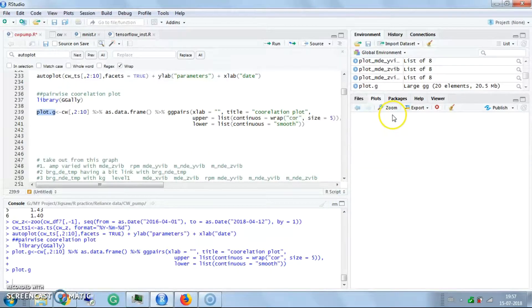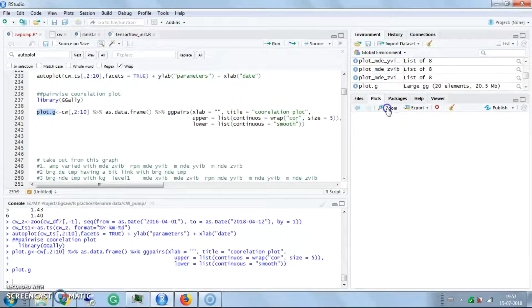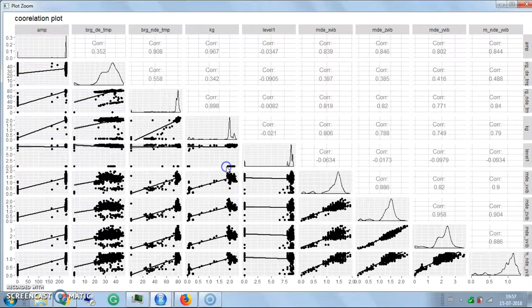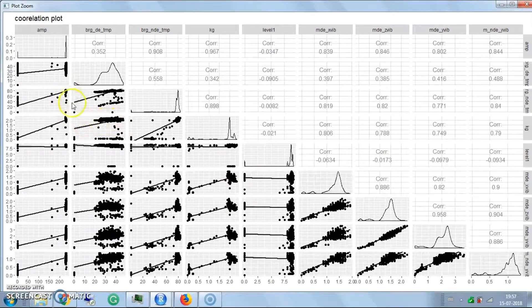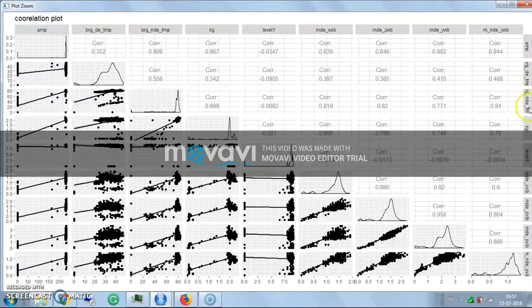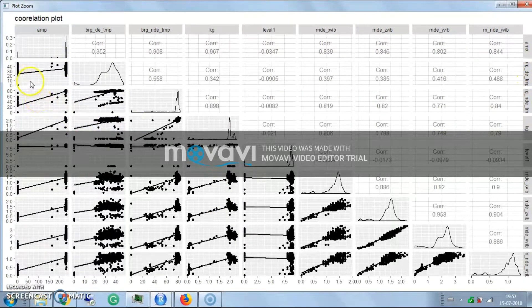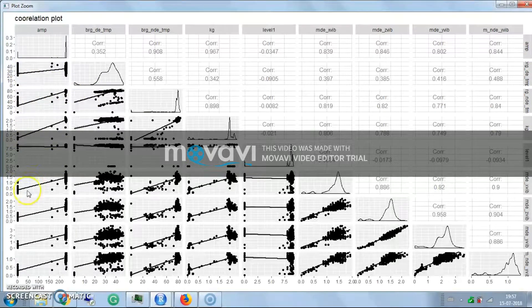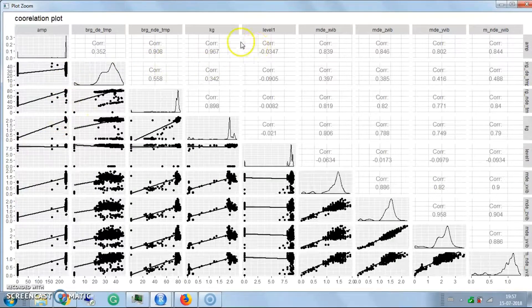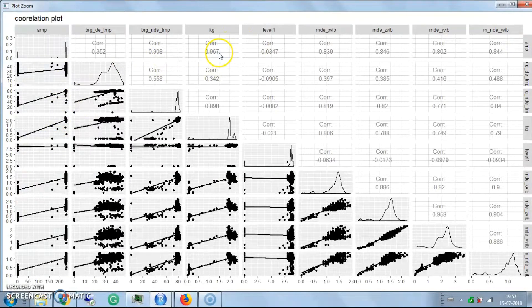Here are the correlations. It shows how ampere is correlated with bearing temperature - you see it's linearly correlated. This shows the correlation value with the percentage.